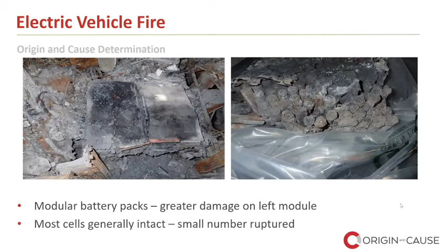Most commonly that's a single cell failure creating excessive heat, leading to thermal runaway in adjacent cells. Thermal runaway is a feedback loop that occurs when one cell has a small failure generating excessive heat, increasing the battery's chemical reaction rate since batteries run faster when hot. That temperature increase leads to higher electrical currents, which leads to more heat, and the loop continues, starting in a single cell and spreading to nearby cells.